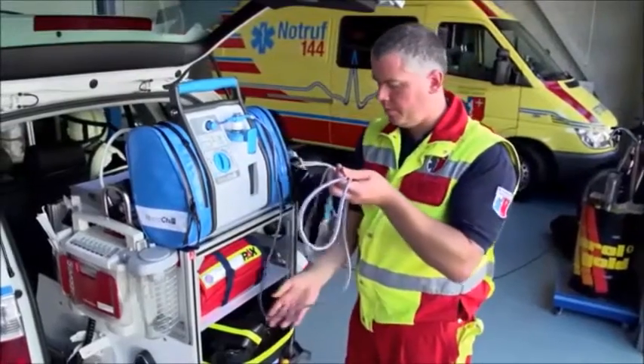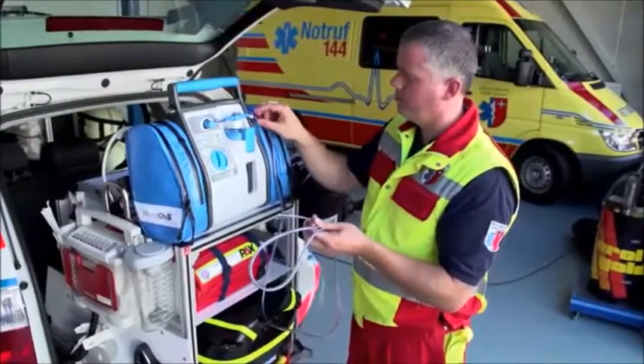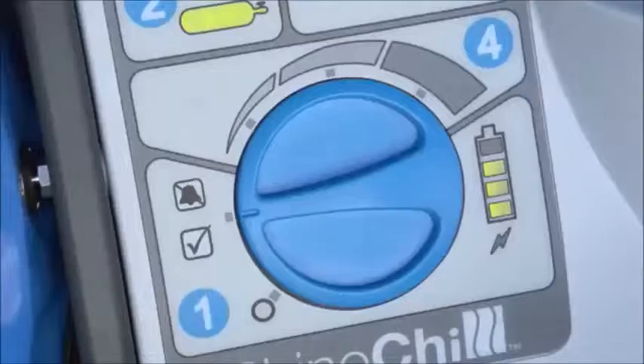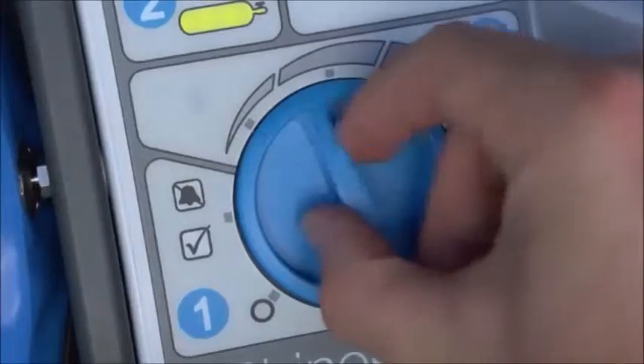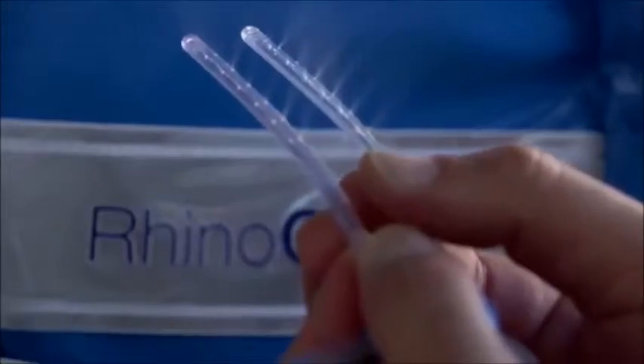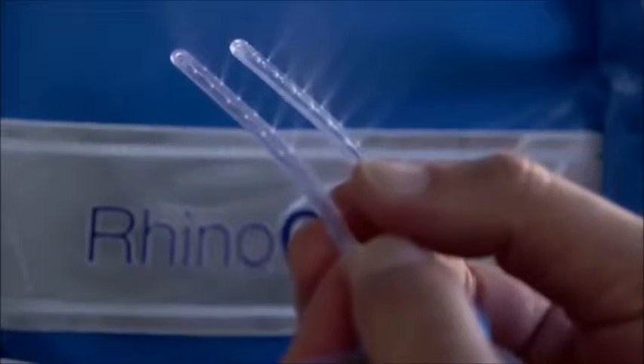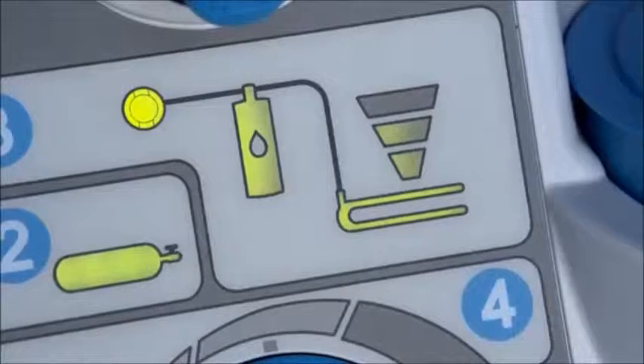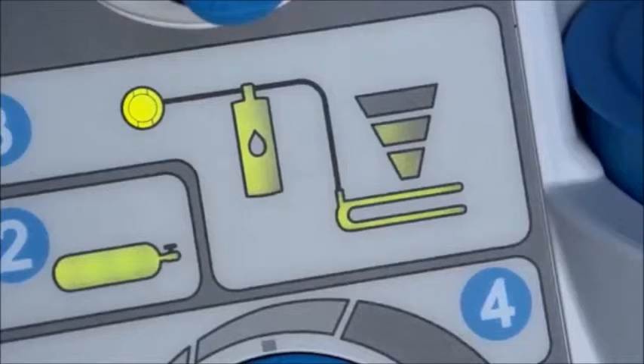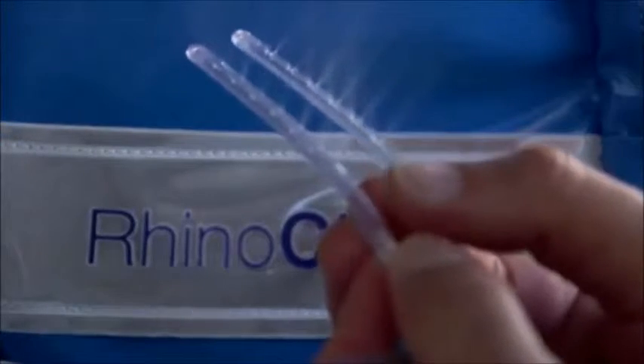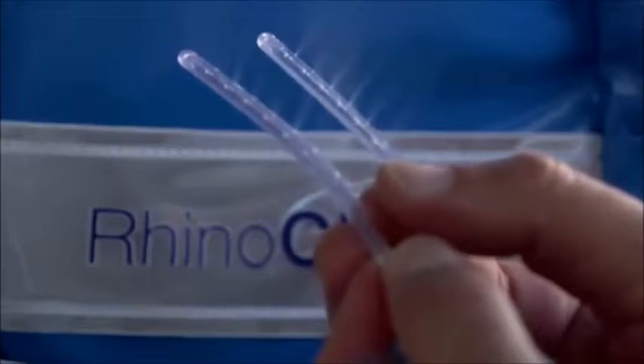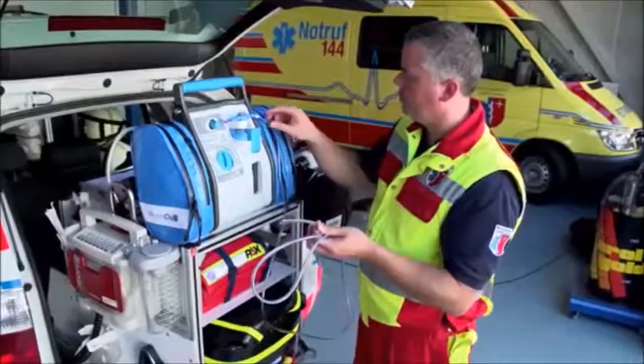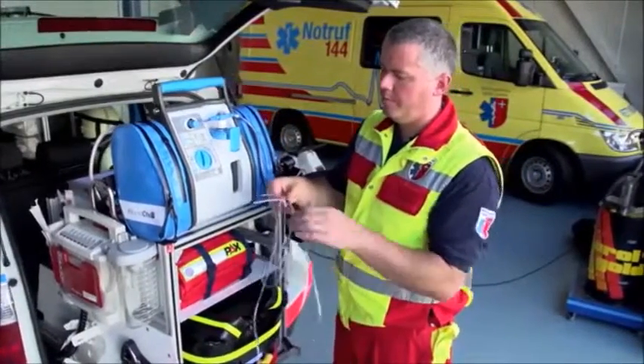Take hold of the catheter by the cannula hub so that the nasal cannula are pointing away from you. Move the setting control knob to the medium setting. Confirm that the spray is emitting from all ports on each of the cannula and that the nasal cannula indicator light illuminates green. There may be a slight delay of a couple seconds before spray is seen while the catheter is primed with the liquid. Confirm that there are no leaks in any part of the catheter.